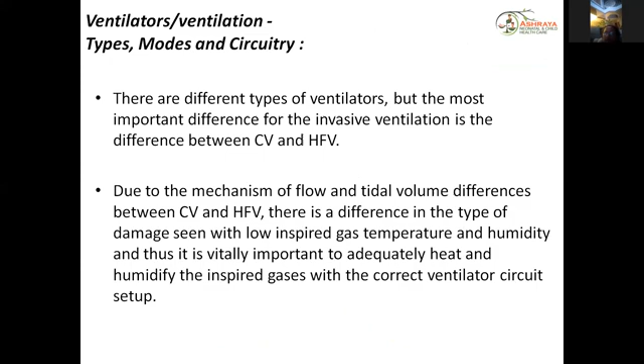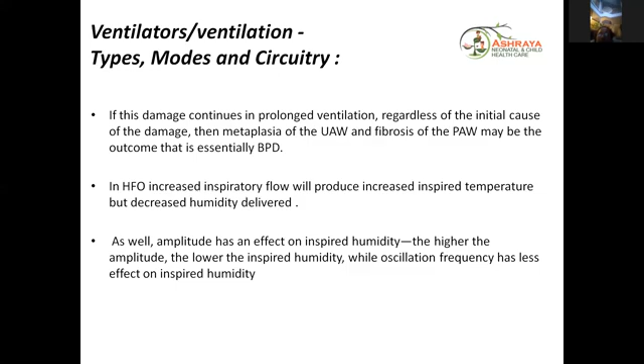If this damage continues in prolonged ventilation, regardless of the initial cause of the damage, then metaplasia of the upper airway and fibrosis of the peripheral airway may be the outcome, and that essentially leads to BPD. In high frequency oscillation, increased inspiratory flow will produce increased inspired temperature but decreased humidity delivered. As well, amplitude also has an effect on the inspired humidity. The higher the amplitude, the lower the inspired humidity, while oscillation frequency has less effect on the inspired humidity.